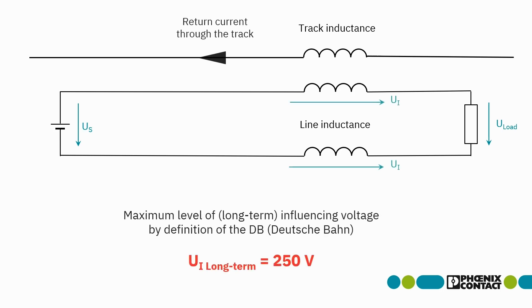The level of the influencing voltage depends, for example, on the traction current or the influenced cable length. Deutsche Bahn has defined it as 250 Volt. It is permanently present and is therefore called the long-term influencing voltage.